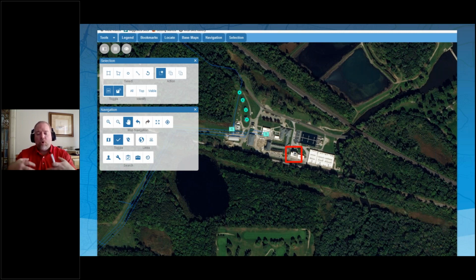So the whole purpose we went through this is we needed to get away from the scheduled PM idea and find a way to leverage more appropriate SOPs, or the true information caused throughout our system, and to take advantage of this large system called SCADA that runs most of our real-time operations but isn't leveraged by any workflow outside of the SCADA system. So now, instead of an oil change PM inside Cityworks for pump number 1 at the high lift pump station sitting there waiting every 3 months, we're taking advantage of the real data.